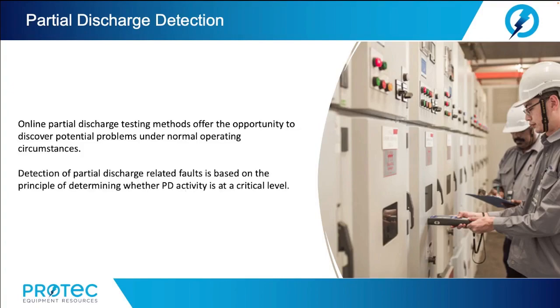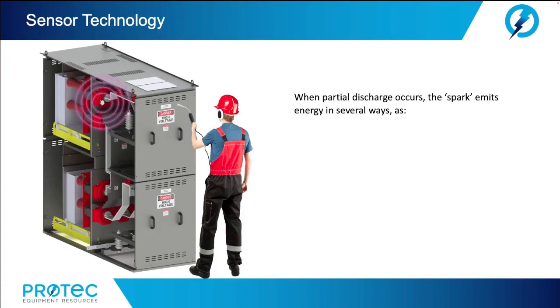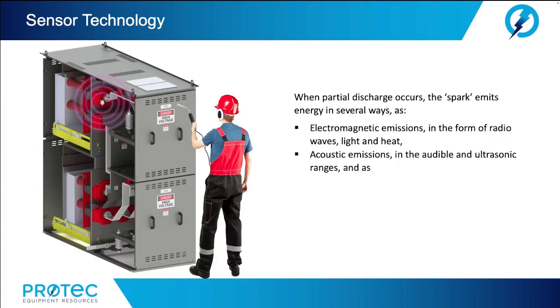Detection of partial discharge-related faults is based on the principle of determining whether PD activity is at a critical level. Low levels of partial discharge activity are often present in assets at levels which may be considered acceptable, for example, non-critical or unlikely to develop into failures in the short to medium term. When partial discharge occurs, the spark emits energy in several ways: as electromagnetic emissions in the form of radio waves, light, and heat; acoustic emissions in the audible and ultrasonic ranges; and as ozone and nitrous oxide gases.